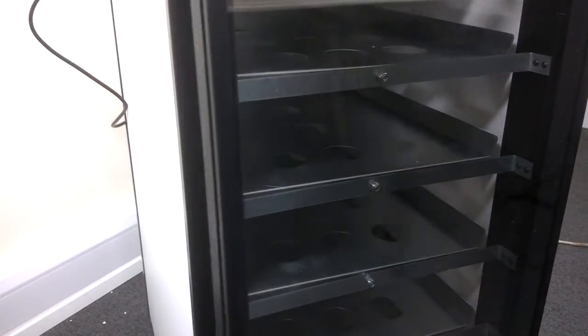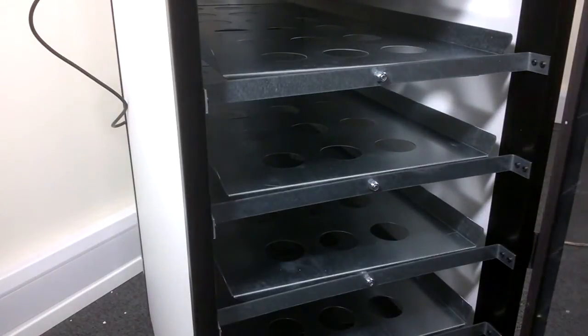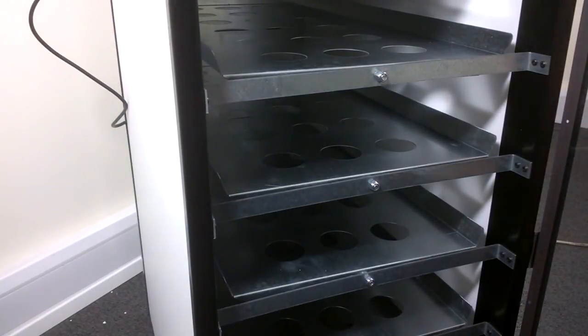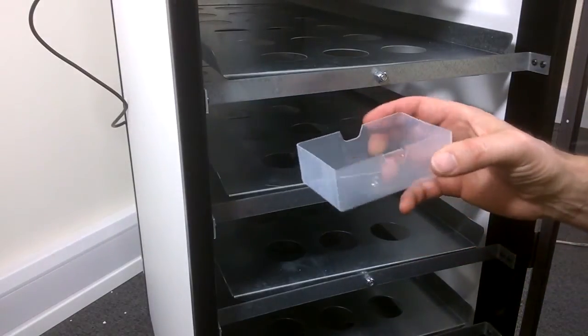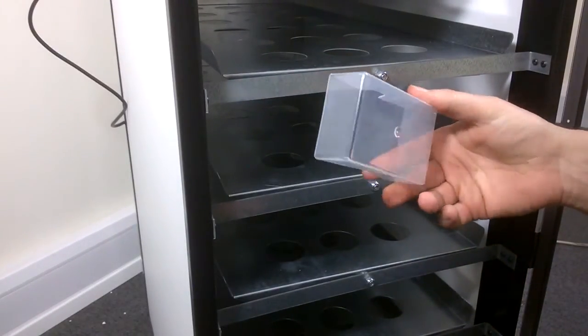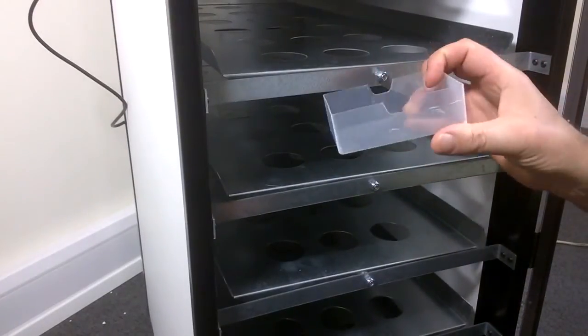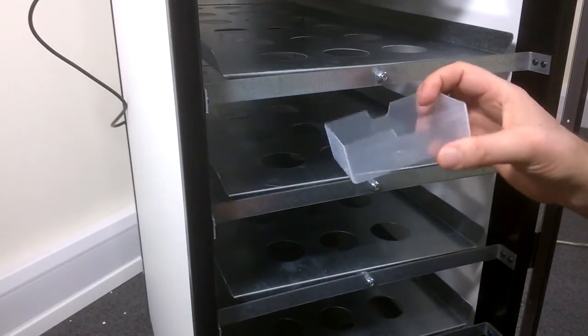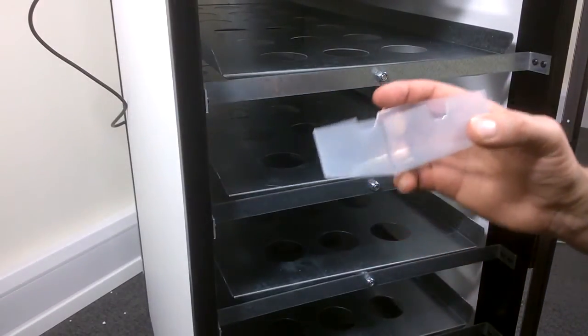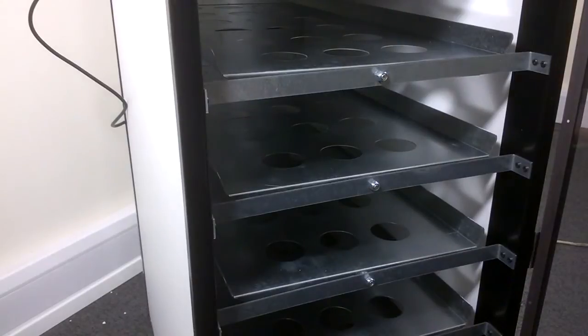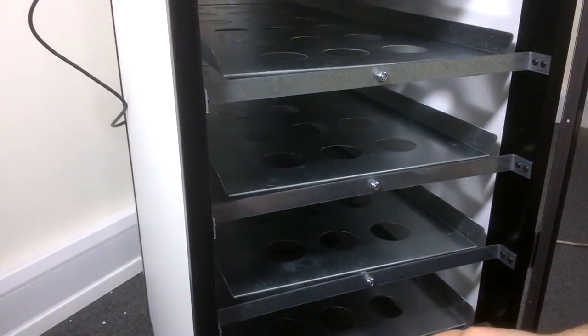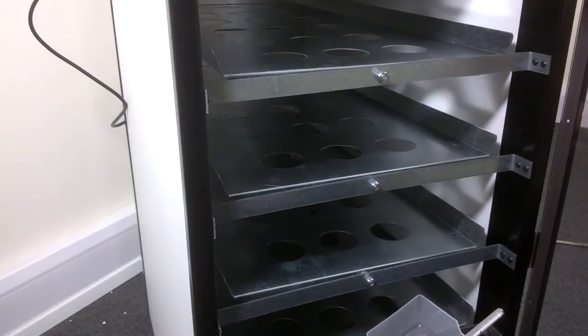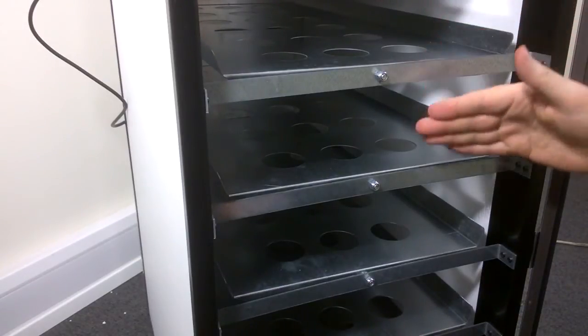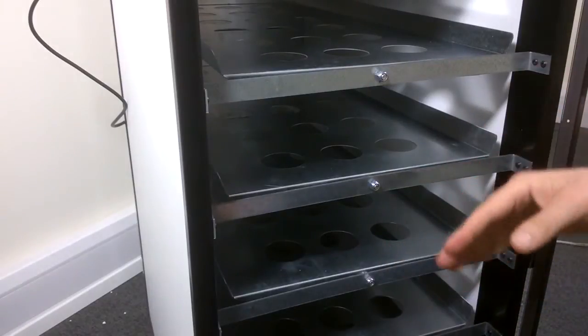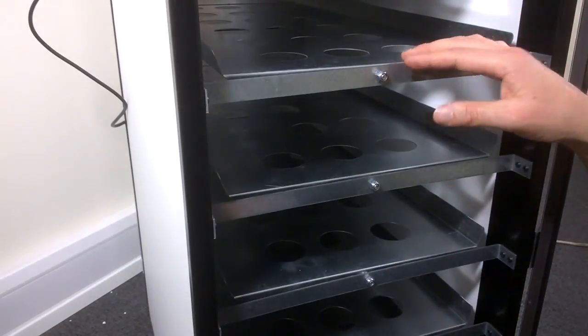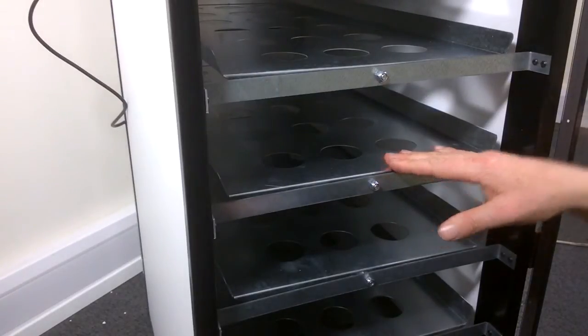Okay, so let's open our OVAEASY because we want to put our thermometers in there. So we need something that's 30 millimeters high. What I'm using in this case is not a little wooden block, it's actually a business card holder, which happens to be really nicely designed for it. It's 30 mils high. I take my thermometer and I place my thermometer in the machine. On the OVAEASY 580, I'm looking for the third shelf down. On the OVAEASY 190, I'll put it on the top shelf. On the 380, I'll put it on the second shelf, which is the middle shelf. So this is a 580 machine.